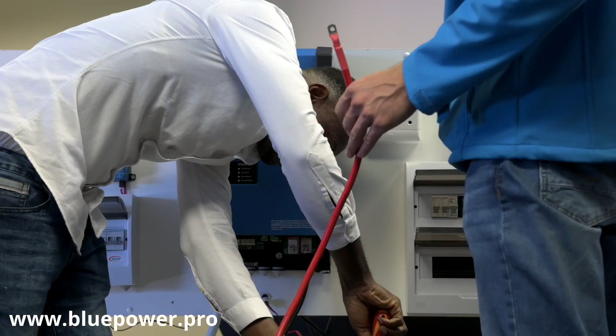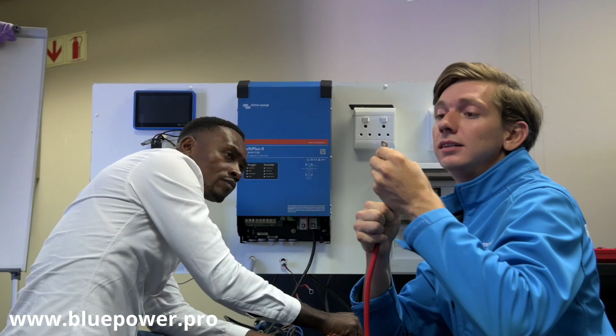There you go. We can just take that one there. Now this one has got a wrong lug. Just quickly, there's a bigger lug there. Just quickly turn it off for me there. Make sure you also use the right size lugs on your DC cables. Is that a 5? A 6. So if you have a 6mm lug and you've got an 8mm connection, you can't drill the lug to make it bigger, because the lug is sized to be 25 by 6. It's not a 25 by 8, so the carrying capacity is going to be reduced.